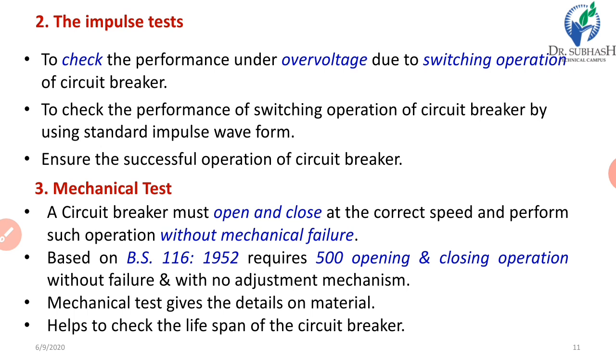Now the second one is the impulse test. It is used to check the performance under over voltage due to switching operation of the circuit breaker, and to check the performance of the switching operation of the circuit breaker by using a standard impulse waveform. Another objective is to ensure the successful operation of the circuit breaker.